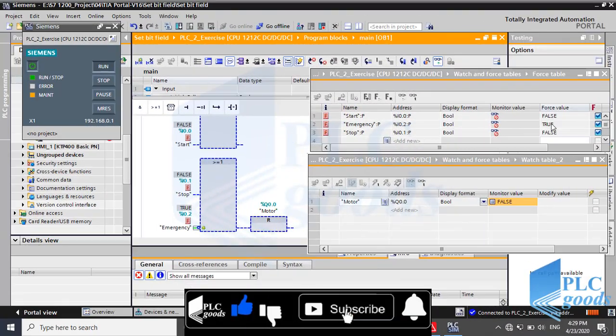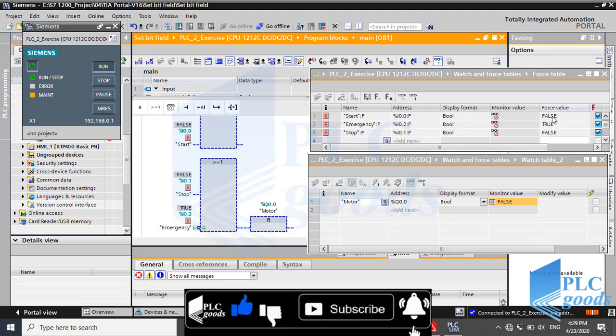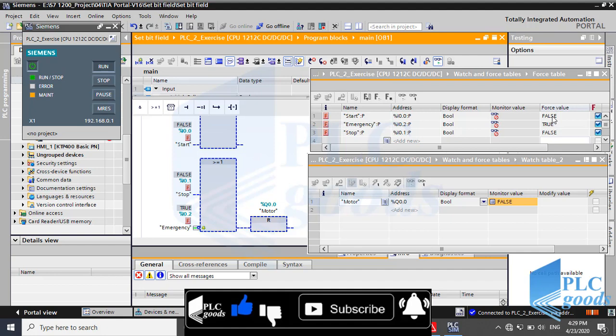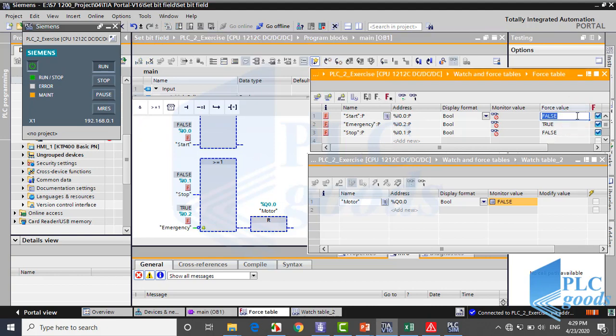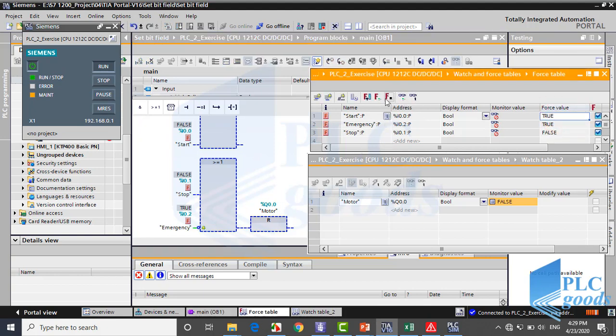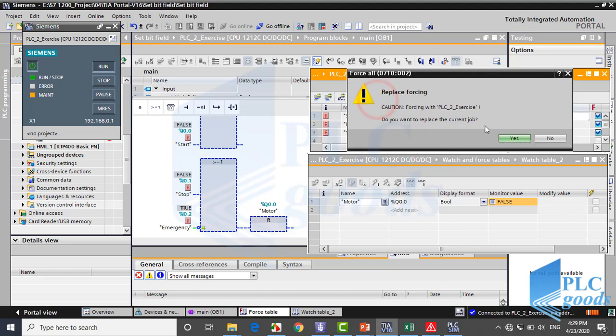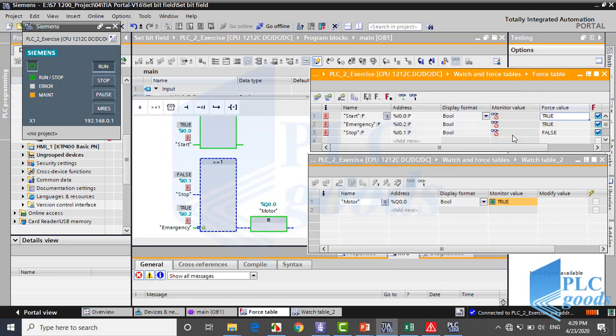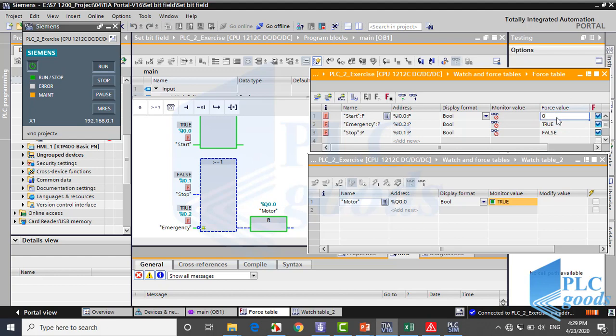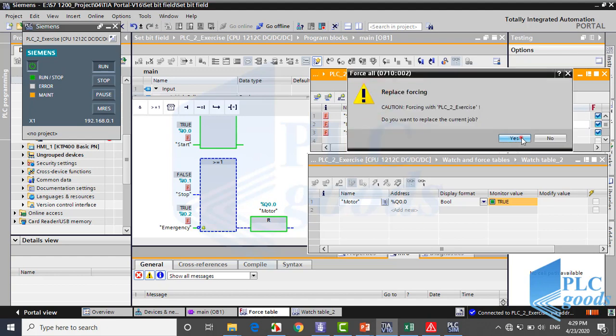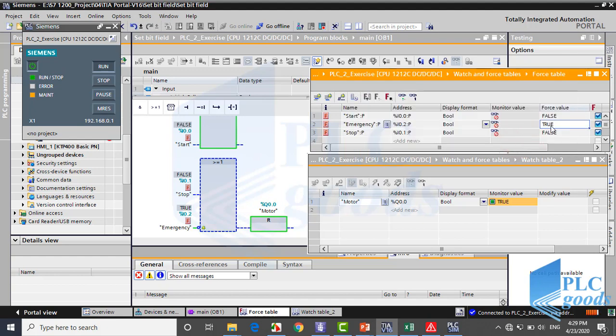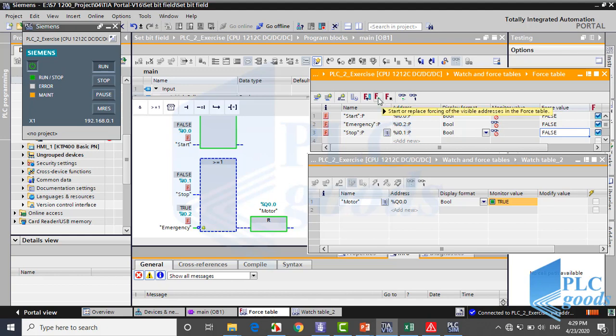Now let's simulate this program like previous projects. As you see, when PLC is started with its normal conditions, I0.0 and I0.1 are false and I0.2 is true. Watch table shows the motor is off. When start is activated, motor will be on. And now if emergency push button is pressed, respectively the I0.2 address changes to 0, the output will be off.